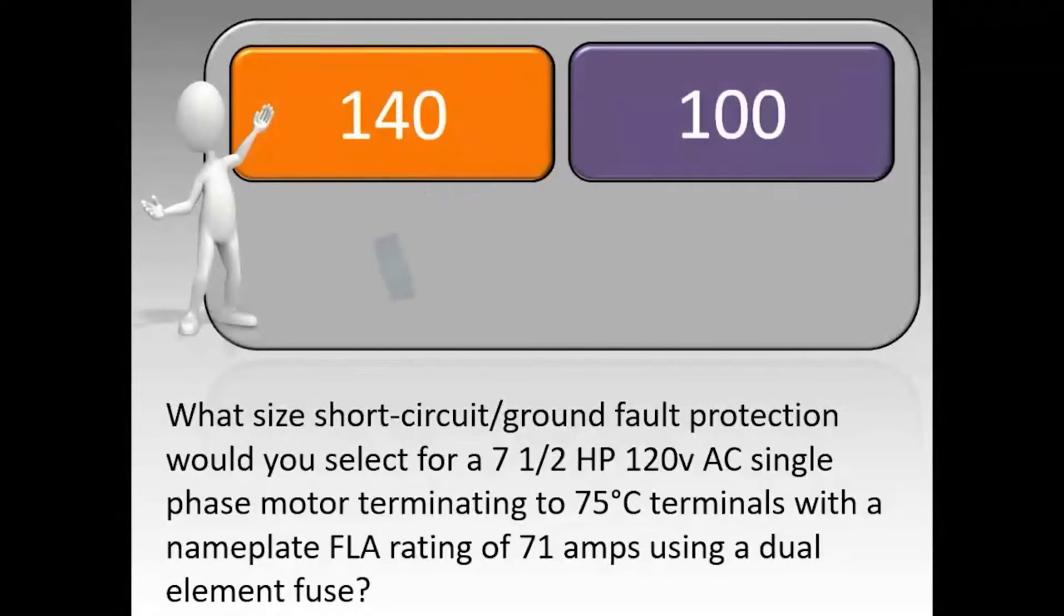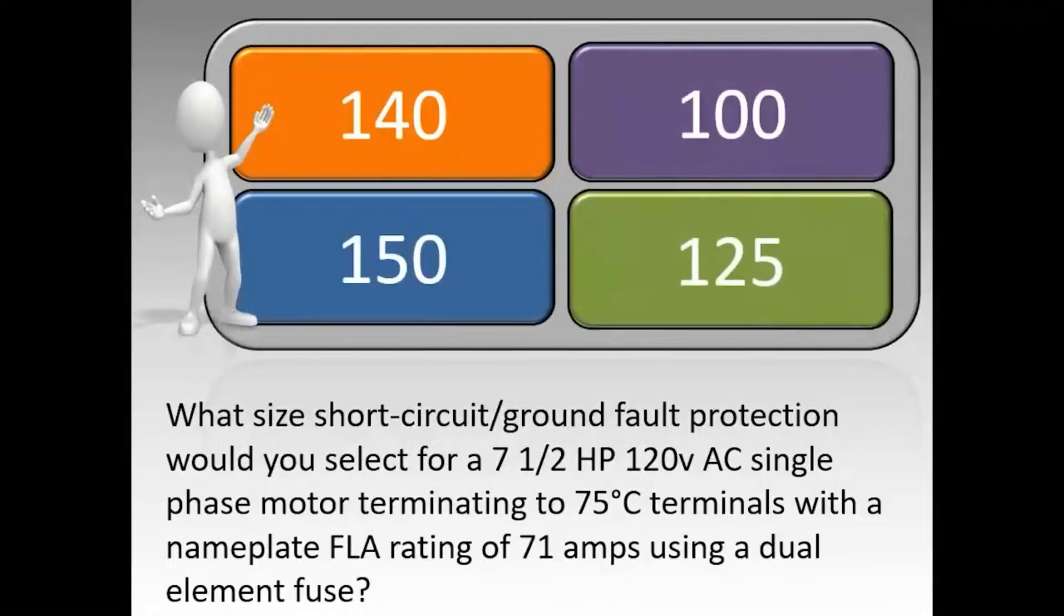What size short circuit ground fault protection would you select for a 7.5 horsepower, 120 volt AC single phase motor terminating to 75°C terminals with a nameplate FLA rating of 71 amps using a dual element fuse?